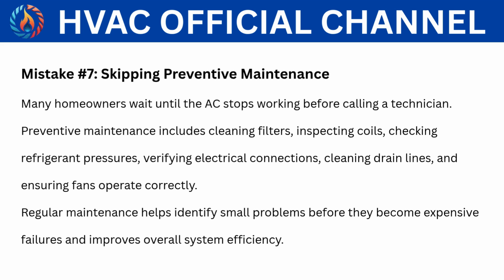Mistake number 7. Skipping preventive maintenance. Many homeowners wait until the AC stops working before calling a technician. Preventive maintenance includes cleaning filters, inspecting coils, checking refrigerant pressures, verifying electrical connections, cleaning drain lines, and ensuring fans operate correctly. Regular maintenance helps identify small problems before they become expensive failures and improves overall system efficiency.